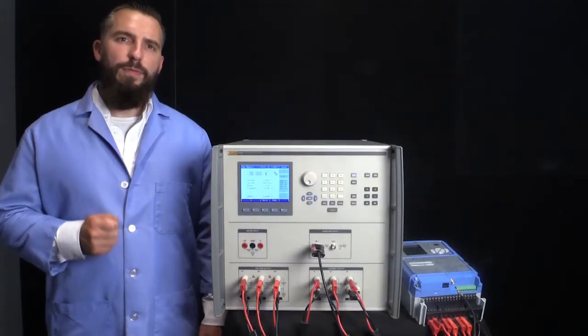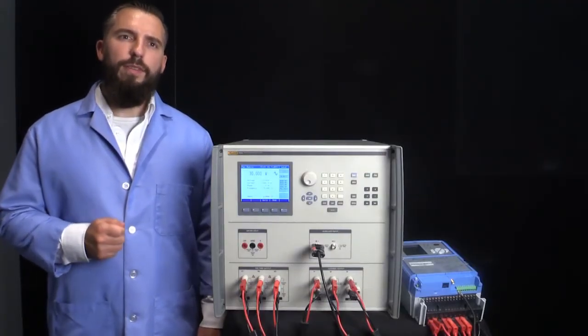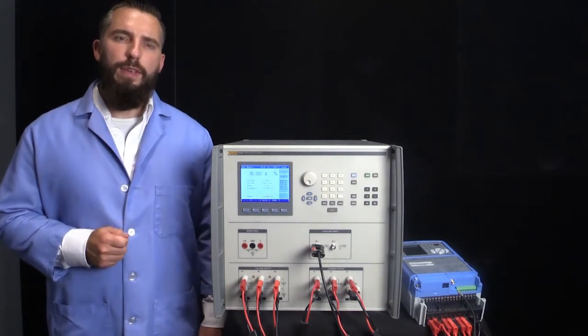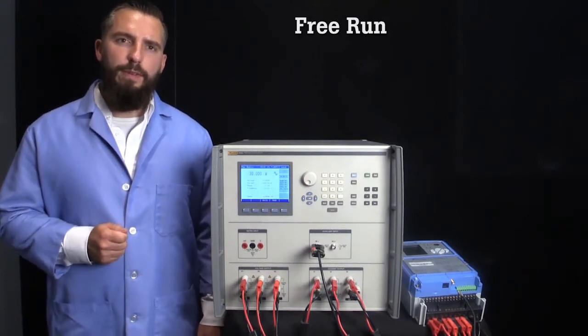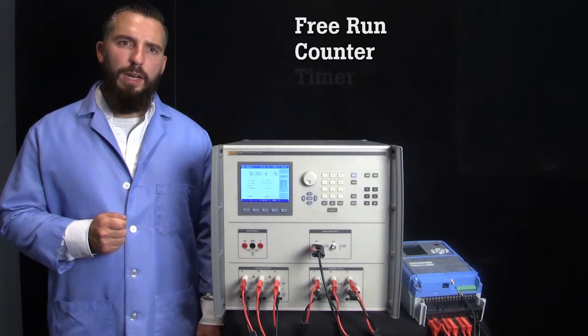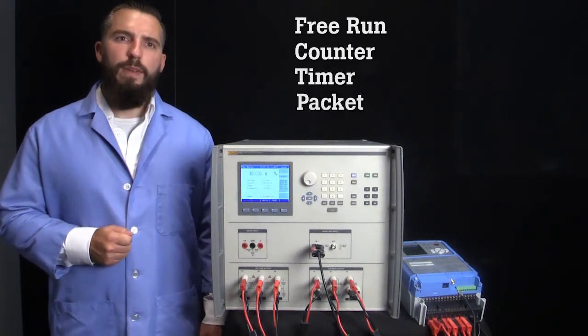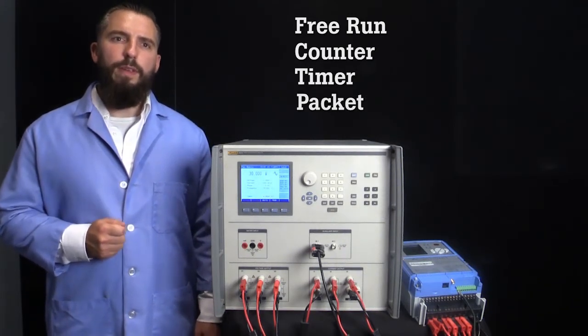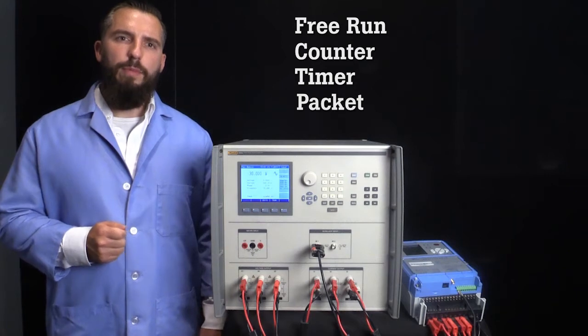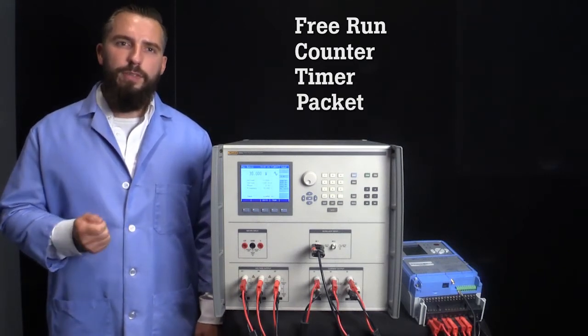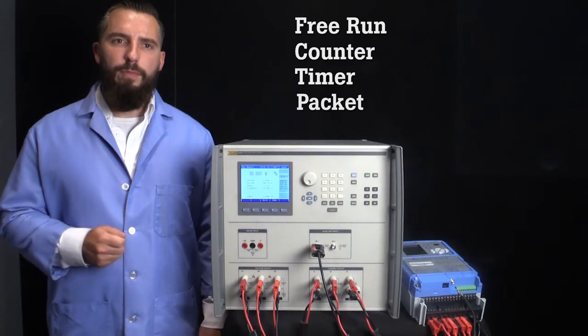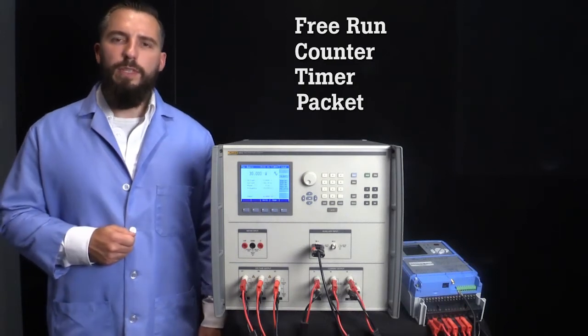The 6003A has four energy testing modes that allow you to test a variety of energy meters. Those modes are free run, counter, timer, and packet. All of these modes provide a way of easily configuring a test to output a precise power level. In return, the energy meter will provide a watt-hours measurement. Let's discuss these modes in more detail.